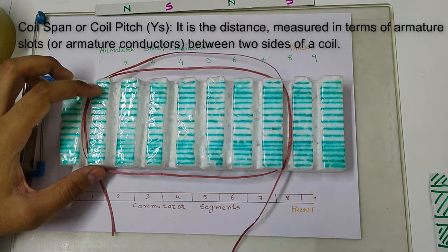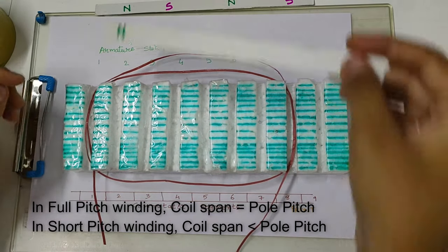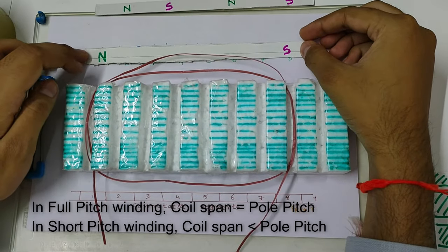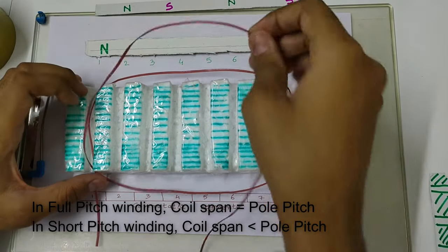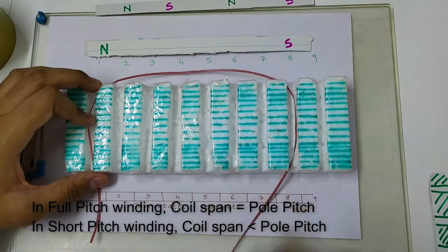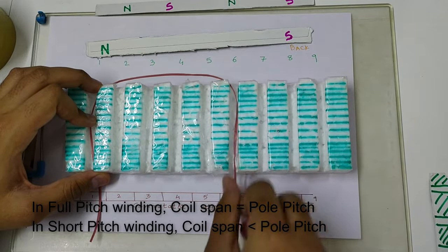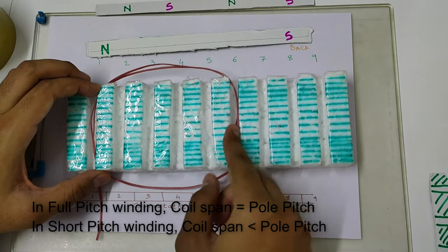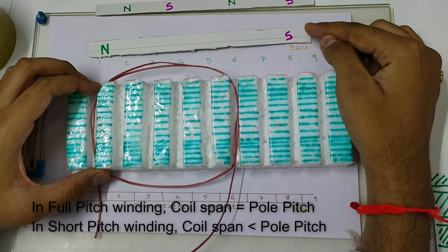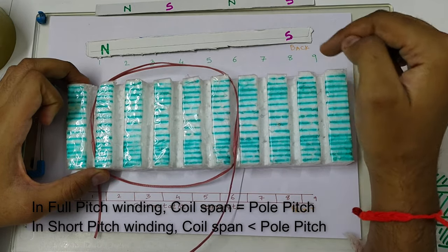Now, if coil span is equal to pole pitch, then this type of winding is called a full pitched winding. And if coil span is less than pole pitch — say for example if pole pitch is 8, but my winding starts from 1 but ends at 6, then the other side of the winding is not reaching the south pole. In such a case, this winding is called a short pitched winding.